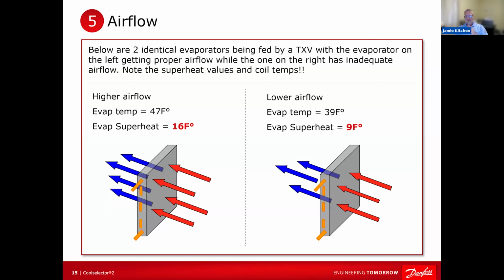So airflow, big deal. So if you happen to have, let's say, proper airflow. All right, it's an air conditioning system. You're running at 47 degrees. I show 16 degrees of superheat. You may say, hey, that's a lot of superheat. Not really. If you have a lot of humidity in the air, right, that can drive your superheat up. That just tells you that valve is throttled open. All right, and you'll see that superheat start to drop. 15, 14, 13, whatever. Now remember, superheat in air conditioning is not the same as superheat in refrigeration, because you got a 35, 40 degree temperature difference between the air and the coil in air conditioning. You can afford to have a lot more superheat than you can in refrigeration.